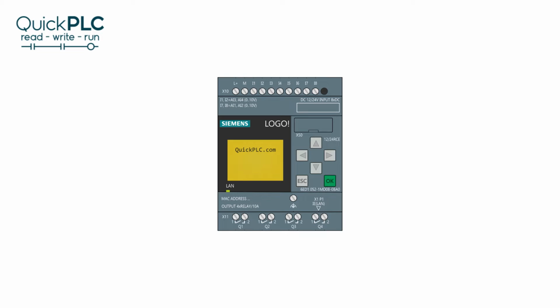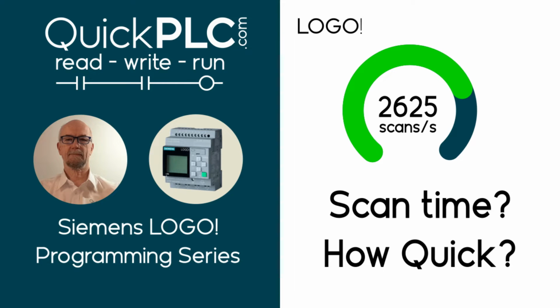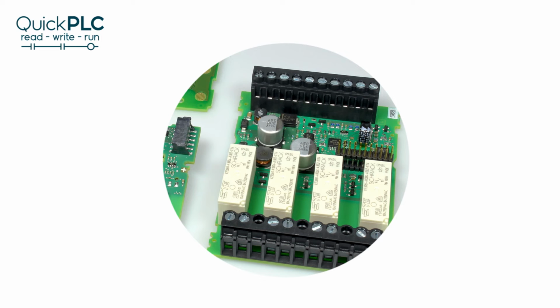Logos with transistor output can switch as quickly as the program will allow. See the How Quick is a Logo video linked below for more on that. Logos with relay output will be limited by the response time of the relay and the lifespan due to mechanical wear and any arcing of the contacts.